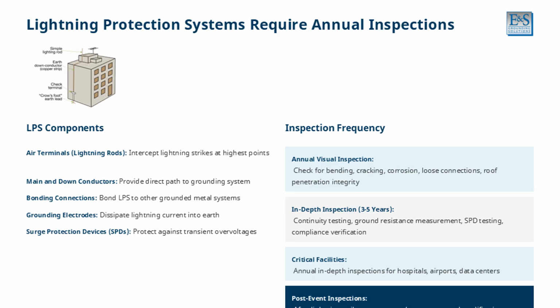Inspection frequency varies by facility type. Annual visual inspections check for bending, cracking, corrosion, loose connections, and roof penetration integrity. In-depth inspections every 3 to 5 years include continuity testing, ground resistance measurement, SPD testing, and compliance verification. Critical facilities such as hospitals, airports, and data centers require annual in-depth inspections. Post-event inspections are mandatory after lightning strikes, severe weather, or structural modifications.